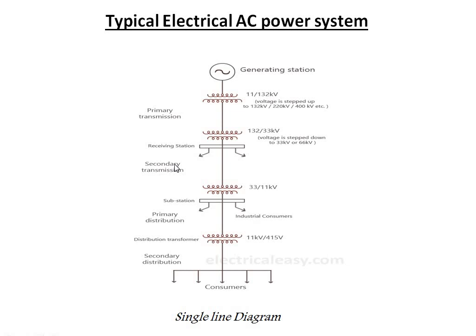This single line diagram can be divided into two phases: the first phase covers primary transmission and secondary transmission, and the second phase covers primary distribution and secondary distribution. After transmission, the power goes to the receiving station where a step-down transformer reduces voltage from 132 kV to 33 kV, or it may be 66 kV. In the primary distribution stage, the voltage is again stepped down from 33 kV to 11 kV. At the distribution side, the voltage level is decreased, whereas at the transmission side it is increased, which reduces losses and is more economical.